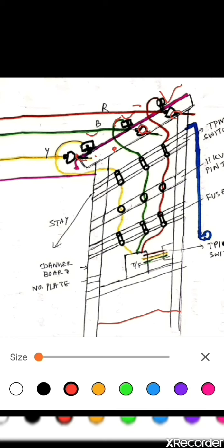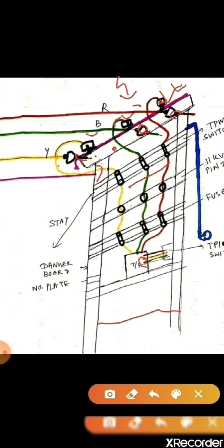And again from this three phase line, the connection is given to this, which is called our TPMO switch. The lightning arrestor is always connected on the top, because if any lightning surge occurs, it will strike directly on the lightning arrestor, so that the transformer will be safe.